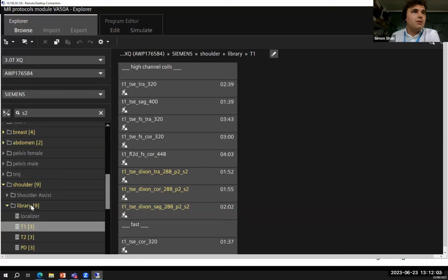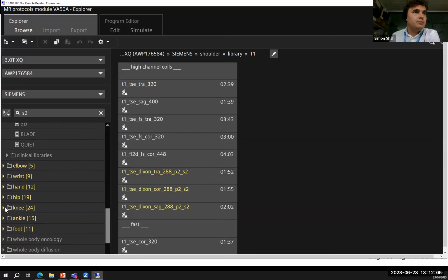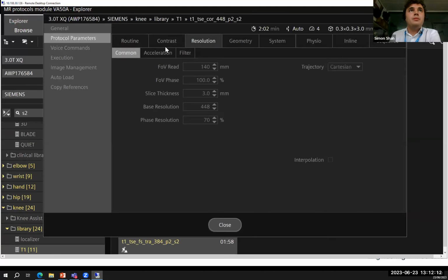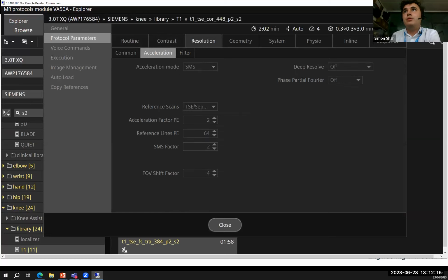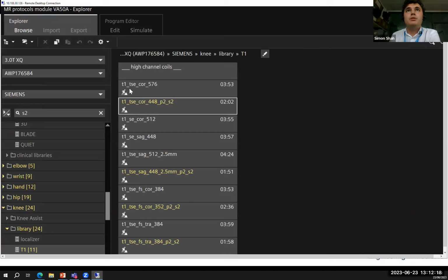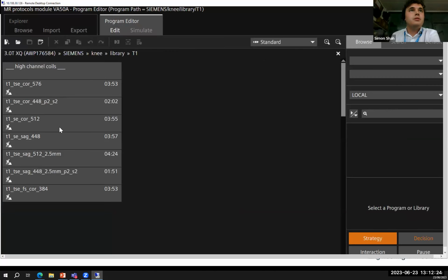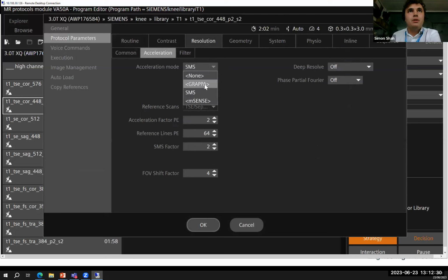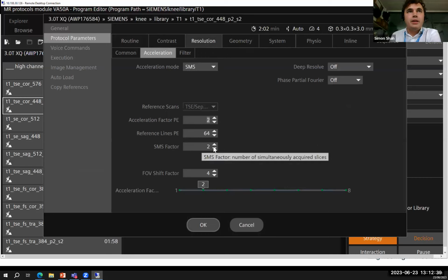So if I go and pull out, I'll tell you what, I'll go to knee. If we go into a scan here, the simultaneous multi-slice is enabled. Oh, I need to go into edit mode. Here we go. So if we open it up, you can see instead of choosing GRAPPA, you can move to simultaneous multi-slice. You can then choose your GRAPPA acceleration, so your phase encoding direction, and then your SMS factor. Again, if you do have Deep Resolve, you can turn it on.